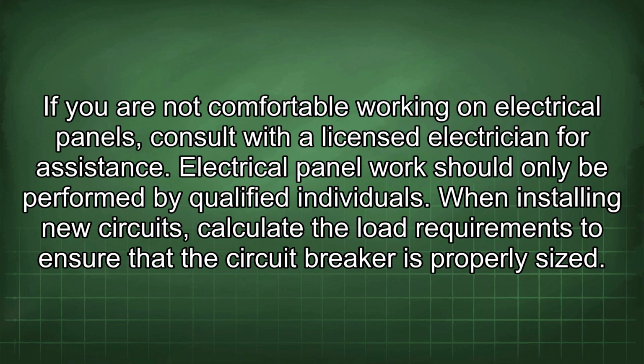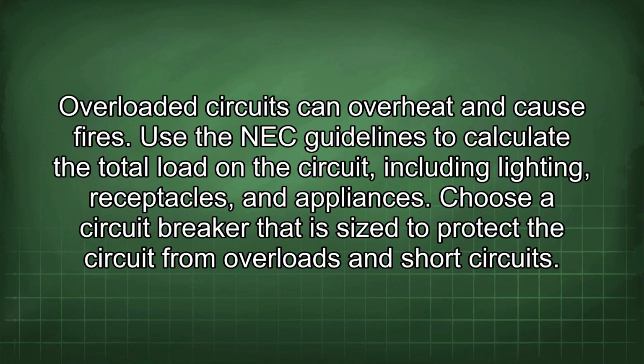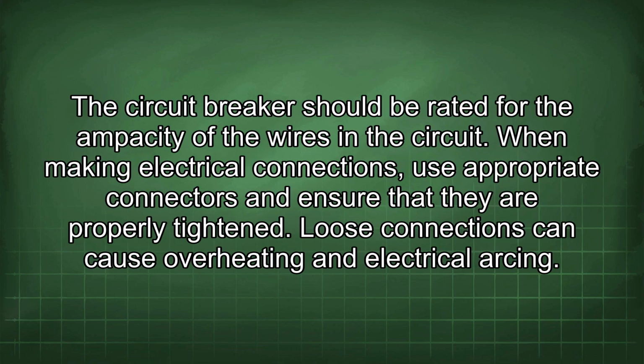When installing new circuits, calculate the load requirements to ensure that the circuit breaker is properly sized. Overloaded circuits can overheat and cause fires. Use the NEC guidelines to calculate the total load on the circuit, including lighting, receptacles, and appliances. Choose a circuit breaker that is sized to protect the circuit from overloads and short circuits. The circuit breaker should be rated for the ampacity of the wires in the circuit.